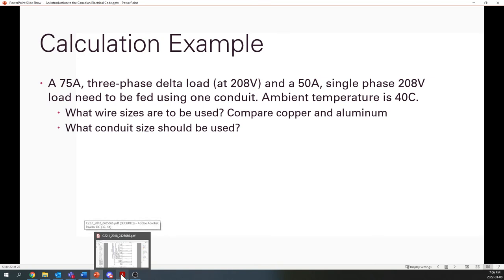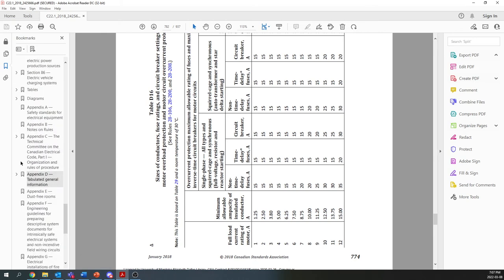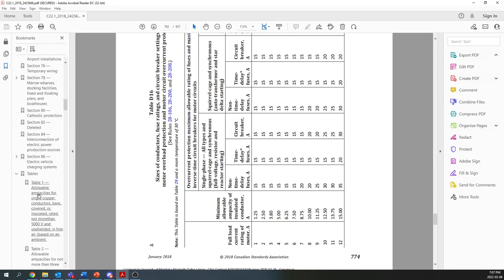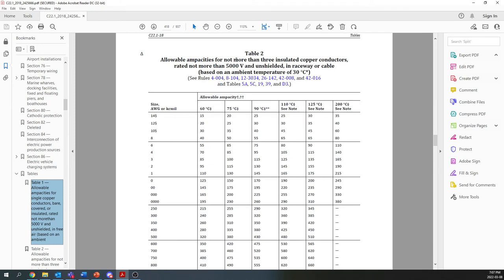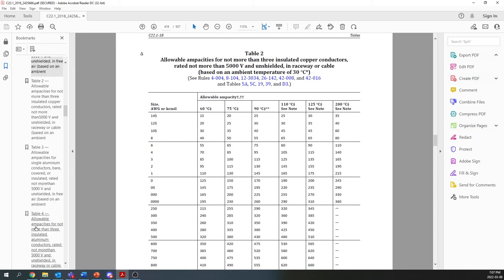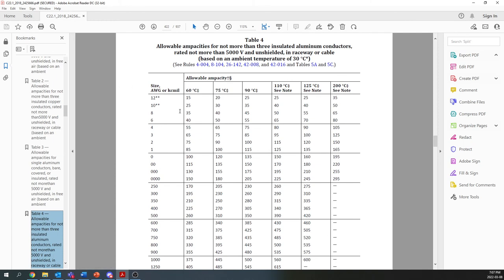So the first thing we're going to do, for your general use, is go to table 2 or table 4 to get your value. Now, here's table 2: not more than 3 insulated copper conductors in a raceway. Again, under 5,000 volts, this is low voltage, and unshielded in a raceway or cable, so your average everyday kind of cable, TECK90, for example. A raceway is just a fancy way of saying a conduit or a cable. And this is for copper. Table 4 is the same thing, but for aluminum. I will leave aluminum as an exercise if you'd like to do that, but we'll do copper together.